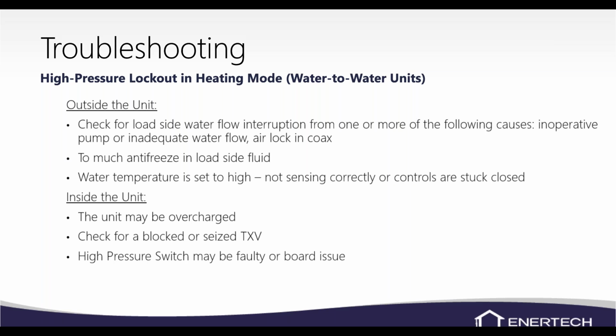Again, TXV, maybe the valve is sticking in cooling or something like that, the reversing valve, but normally with a reversing valve issue, you're not going to see a high or low pressure situation. You're going to more than likely have a capacity issue and your refrigerant pressures are going to look kind of crazy. They won't be equal, but a lot of times they'll be close to equal if it's sticking mid position or something like that.